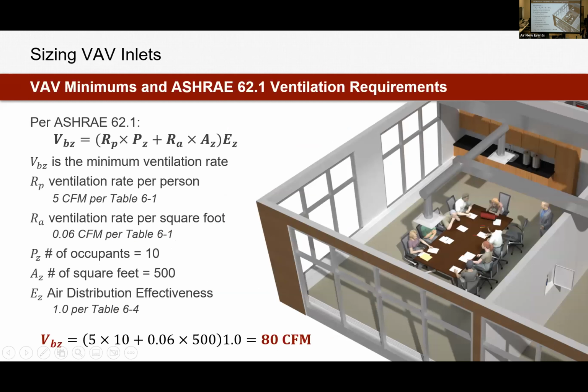So we've sized our inlet valve for a maximum CFM, but we need to check the minimum as well. We need to make sure that airflow readability and controllability will be possible at those lower airflows. So where are we getting our minimum cooling airflow? Minimum cooling is always your ventilation rate in the space. ASHRAE 62.1 gives us equations or factors to be able to determine what that minimum ventilation load is. So for a conference room of this size, the ventilation rate per person is 5 CFM. We can compare that to something like a school classroom. In a school, they require 10 CFM per person. In an office building with adults, 5 CFM per person. ASHRAE doesn't care about adults quite as much as they do children, but you can just see that those ventilation loads are going to change based on what the space is.